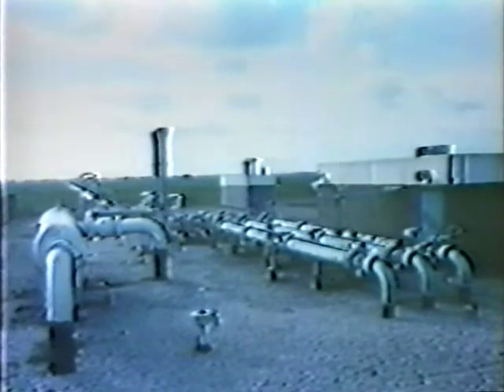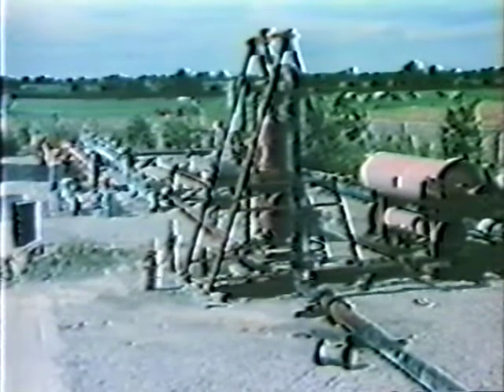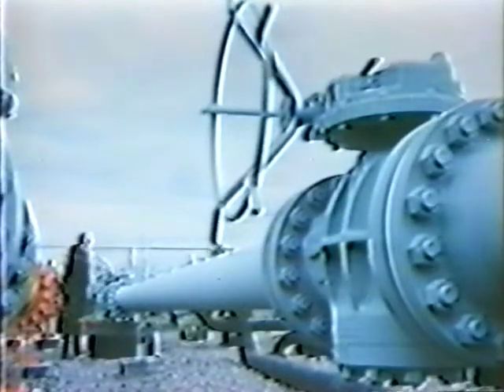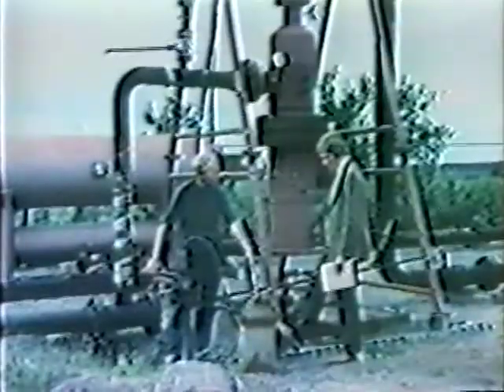Separators are installed at the inlet side of measuring and regulating stations to protect the station against inconvenience from condensate. An arrangement at a measuring and regulating station is used to test the liquid catching efficiencies of the different types of separators under practical conditions. The gas stream passing through the station can be wholly or partly conducted through the testing installation. During a given period of time, liquid is injected into the gas stream flowing towards the separator. The blow-by of the separator is collected and measured.